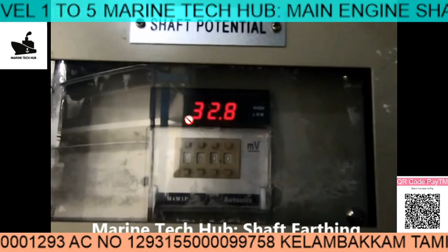When the shaft is rotating, it produces an EMF. This EMF has to be grounded so that it is not transmitted through the bearing. If the grounding is not okay, we will have a lot of problems with the bearing, such as pitting marks. So the purpose of the shaft earthing is to make sure the earthing is proper, so that all the millivolts generated are grounded to the hull.